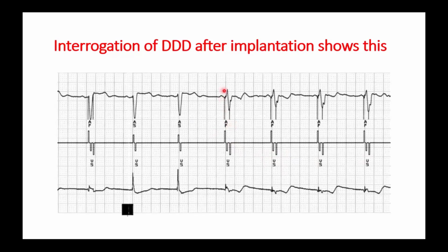Excellent, excellent. The atrial lead is actually sensing the ventricle. And here, when we reach the lower rate interval, the atrial pacing is delivered, followed by a ventricular beat, and actually it captures the ventricle. Here the morphology is different from here. Some sort of fusion beat occurs. And this is a ventricular safety pacing actually. The clue is that the atrium is sensing the ventricle and it captures the ventricle. So it's actually in the ventricle. And here is a pseudo-fusion beat.